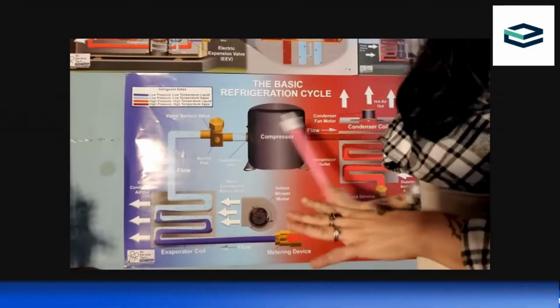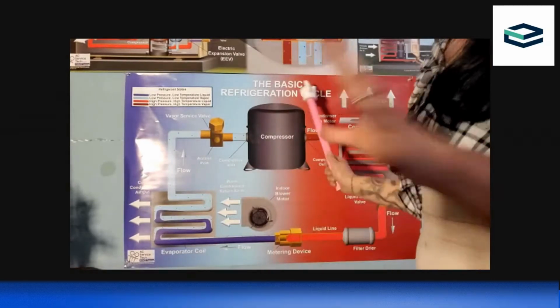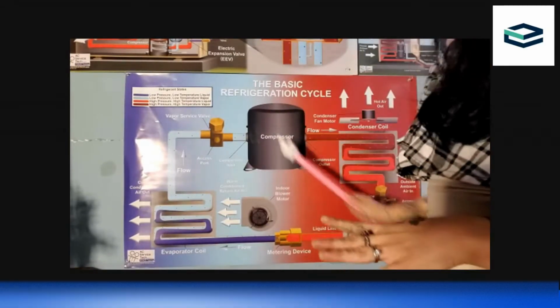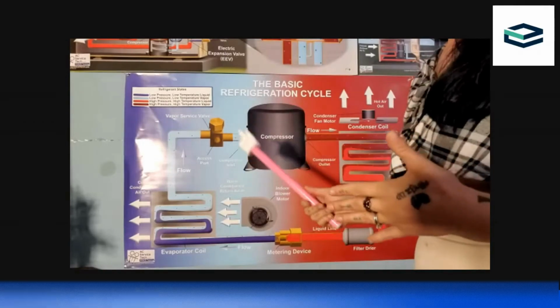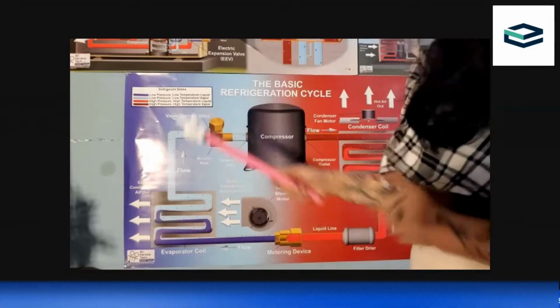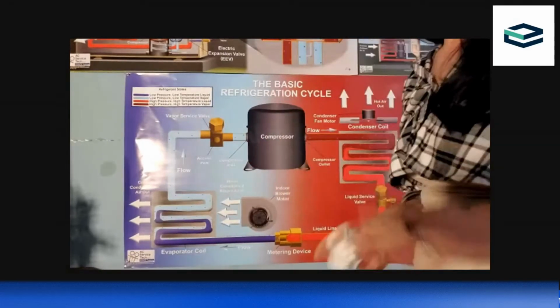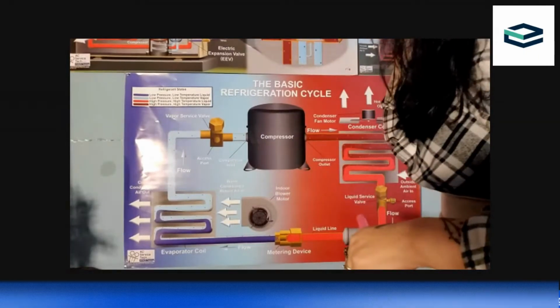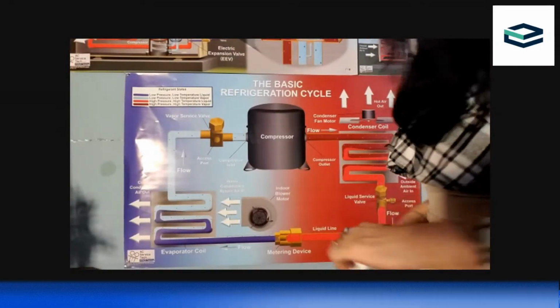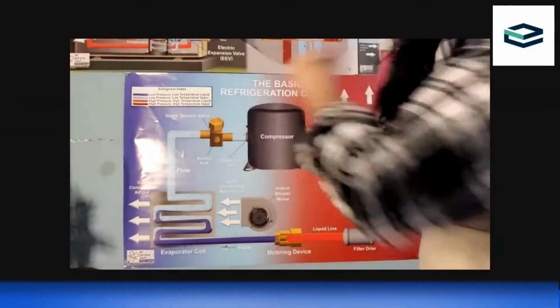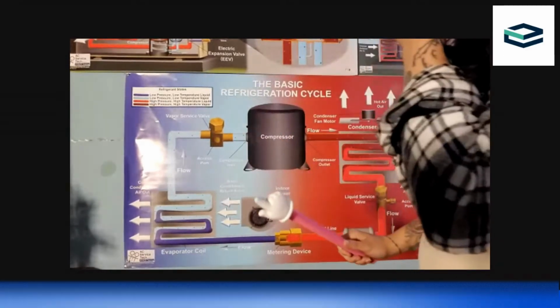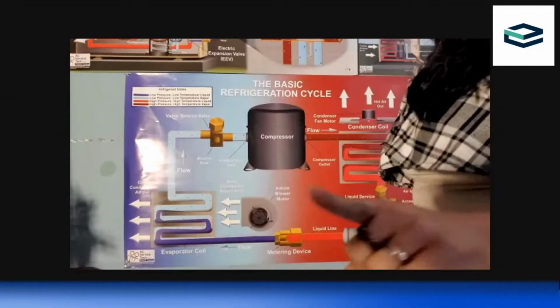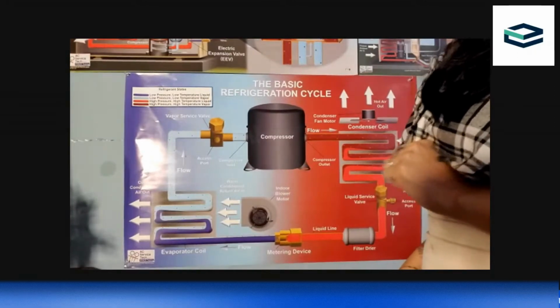So you're going to see a high side under a normal circumstance. You're going to see a high side pressure usually of 300 to 400, and then you're going to see a low side of lower than that, usually in the 120s, 150s, somewhere in there, depending on how your system is built to work. So as you gauge up, you see your high side and your low side pressures. That is only one thing that's being shown on those gauges. The other things are far more important.